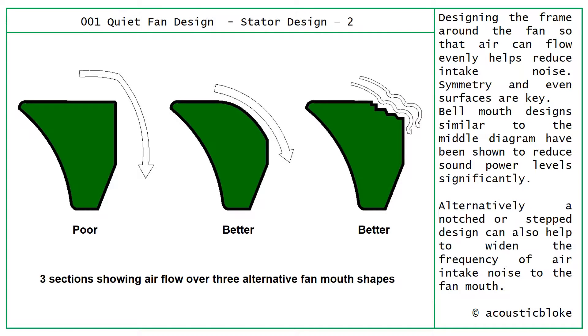Flipping the stator design on its side and cutting a section through it, we can see how air enters towards the fan. Designing the frame around the fan so air flows evenly helps reduce intake noise — symmetry and even surfaces are key. The bell mouth design is similar to what you'll see on most fan systems and has been shown to significantly reduce noise levels. A poor design would have square edges and lack of symmetry. An alternative is a notched or stepped entrance design, which can also help widen the frequency of noise from the fan mouth.